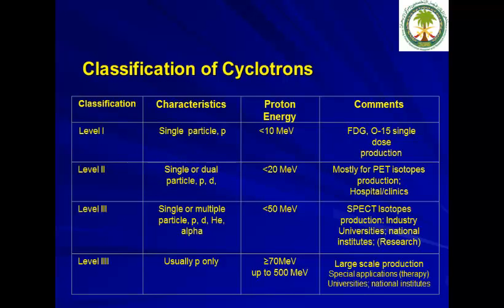How do we classify cyclotrons? I classify them into four different levels. Level 1 is a single-particle cyclotron accelerating protons only, usually less than 10 MeV, used for FDG or oxygen-15 production in single doses. Level 2 is a single or dual particle cyclotron — proton or deuteron — usually less than 20 MeV, mostly producing PET radioisotopes, typically located in hospital and clinical settings.